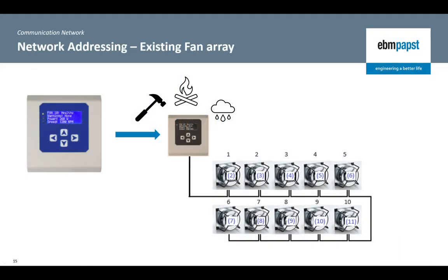The option to install a new MDC controller on an existing fan array should only be used to replace an MDC controller that has become damaged. When this option is chosen, the controller starts the fan search by looking for the first fan with Modbus Device Address 2. Once found, the controller looks for Modbus Device Address 3, 4, 5, and so on until all of the fans in the array are found.